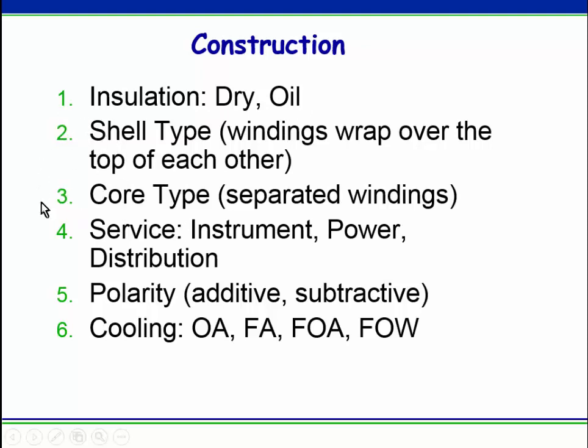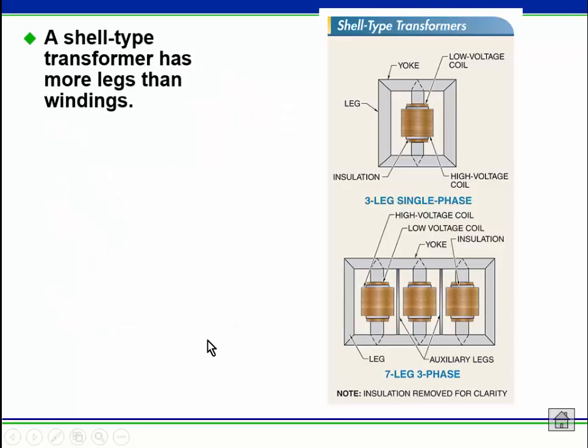This isn't that important for the technician, but you might be curious what the differences are. We're dealing mostly with power transformers, but instrument and distribution transformers are very similar. And we'll mention polarity, and then the cooling becomes very important, these different types of cooling. And we're going to look at that too. So here are the two different construction types. Sometimes you'll see this on a nameplate. It'll say shell type or core type.